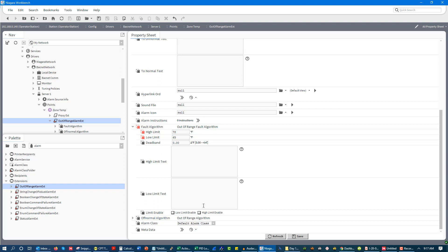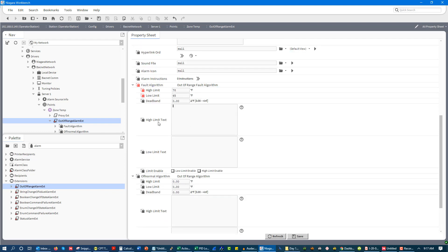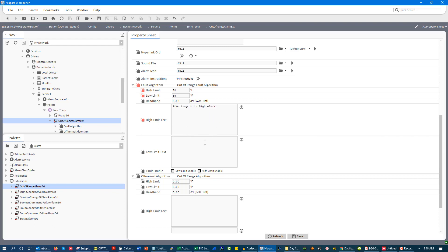And there's on some of these, there's going to be fault and then there's going to be off normal. So off normal is going to be like, hey, you're way out of range. Whereas fault is actually alarm. That's how I like to set them up. And so then I could say, zone temp is in alarm. I'm not going to use any wild cards in here. With this software, you would use some different wild cards in order to, and it's called B format that you would use in order to basically call any objects that are in the system. But we're not going to do that because I don't want to confuse anyone. So I'd say zone is in high alarm. And then, down here, I'd say zone temp is in low alarm. And then if I actually go into an alarm condition, it would then display that. So that is alarms.